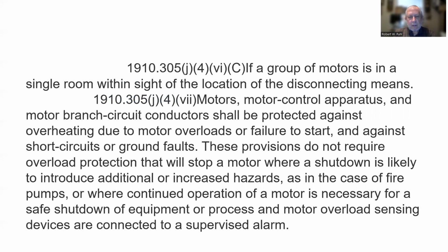of the disconnecting means. Motors, motor control apparatus, and motor branch circuit conductors shall be protected against overheating due to motor overloads or failure to start, and against short circuits and ground faults. These provisions do not require overload protection that will stop a motor where a shutdown is likely to introduce additional or increased hazards, as in the case of fire pumps, or where continued operation of a motor is necessary for a safe shutdown of equipment or process, and motor overload sensing devices are connected to a supervised alarm. So in other words, an overload device doesn't have to shut it down if it's connected to a supervised alarm. People know that it's overloading if it's something that has to be run, like, for instance, a fire pump.